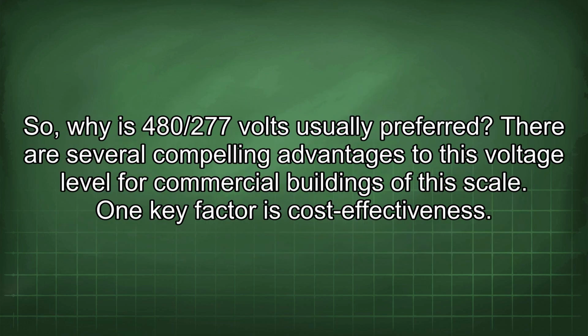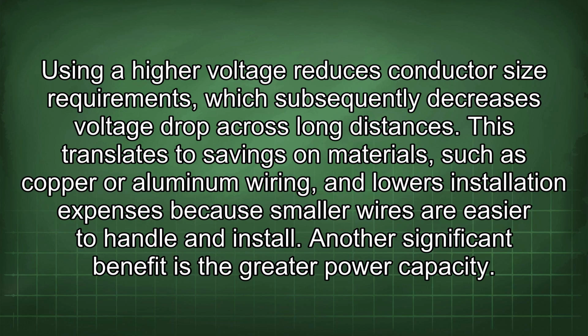So, why is 480/277 volts usually preferred? There are several compelling advantages to this voltage level for commercial buildings of this scale. One key factor is cost effectiveness. Using a high voltage reduces conductor size requirements, which subsequently decreases voltage drop across long distances. This translates to savings on materials, such as copper or aluminum wiring, and lowers installation expenses because smaller wires are easier to handle and install.